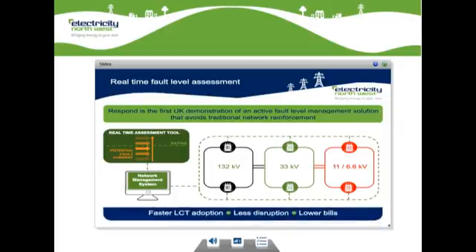Our current network management system allows us to safely control and operate across the different voltages of our network. But currently, it does not have the capacity to perform network studies, which are done using different offline tools. Respond will enhance the functionality and data within our new network management system to include that element of work, the ability to study and assess fault levels. This additional functionality is known as the Fault Level Assessment Tool, and it will hold all the ratings information of our equipment and will calculate fault levels in near real time.